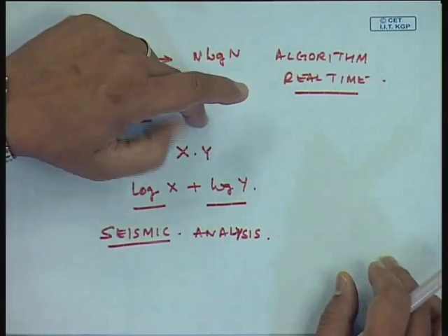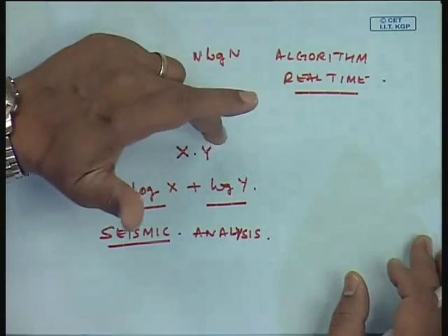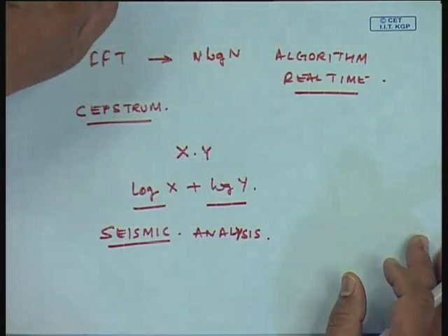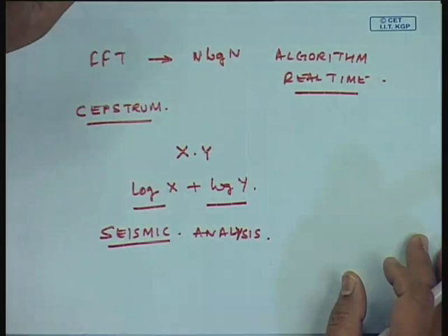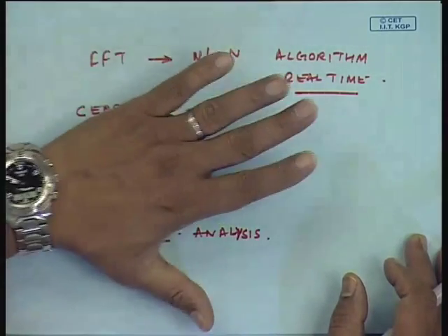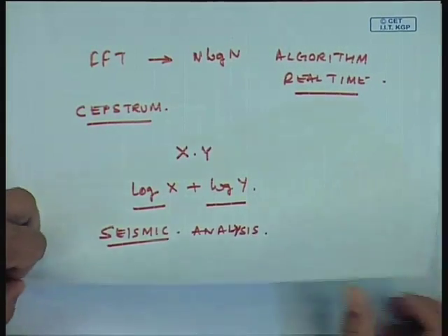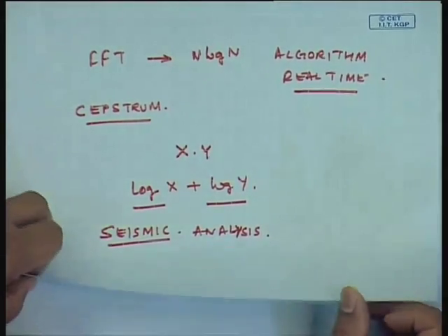Here we will see the same also happens. Suppose I have a large gearbox, a lot of signal contamination occurs because of the path, whether it is coming from the location, through bearing A, or through bearings A, B, C. All those effects will be easily removed once we do cepstrum. So, to summarize, cepstrum is a powerful method to find sidebands in modulated signals.